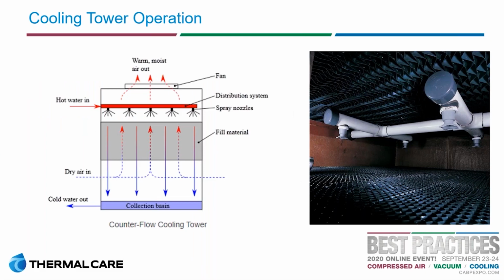So what we're showing here, on the diagram on the left, is a cooling tower and how it would operate. As you can see, this is depicting what's known as a counterflow cooling tower. The hot water comes in the top there on the left with that red bar across it, and those are sprayers. If you look on the right at that photograph, that's a distribution tree, or distribution piping, that would be inside of a cooling tower.